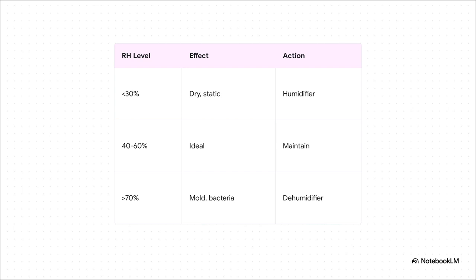Well, operating outside the ideal relative humidity range of 40 to 60% introduces severe biological and mechanical risks. In that sweet spot, humans are comfortable, and the risk of bacteria or viruses is low. But if you drop below 30%, it's way too dry. You get respiratory irritation and static electricity, which is incredibly dangerous around sensitive electronics and volatile chemicals. Go above 70% and it's far too humid. You risk rapid mold growth, condensation on the walls, and massive bacterial proliferation. A humidity failure is, without question, a GMP failure.